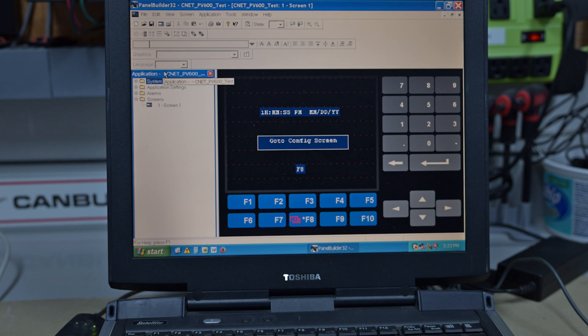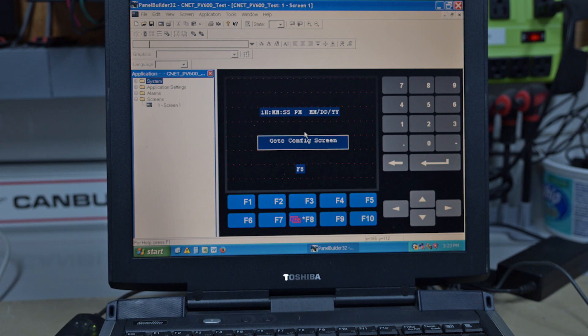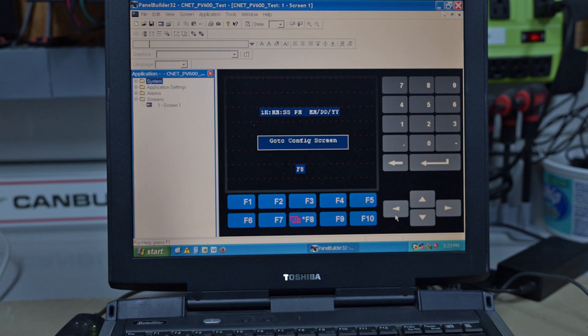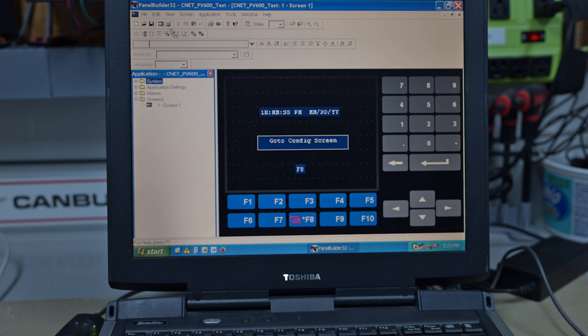So now if we go Open and there's our file. All it's got is one screen with time and date on it and a go to configure screen. Now if you don't have a go to configure screen on your Panel View, if you have keypad, you press the left and right arrows at the same time and it'll take you into the configuration screen, which we'll have a look here in a minute.